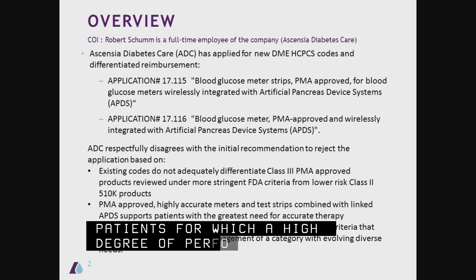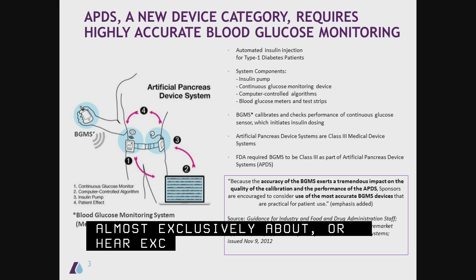You've already heard this morning about how an artificial pancreas system, as defined by the FDA, works. Importantly, we're talking almost exclusively about, or here exclusively about, type 1 patients for whom carefully managed insulin delivery is a necessity of life. Most of the components you've heard about already, an integral component here as well is a blood glucose meter and test strips used for calibration 4 times per day and the checking of the CGM sensor as well as bolus insulin dosing. These artificial pancreas systems are classified as Class 3 medical device by the FDA, and as such, the blood glucose monitor must also fit that classification in order to be part of that system.